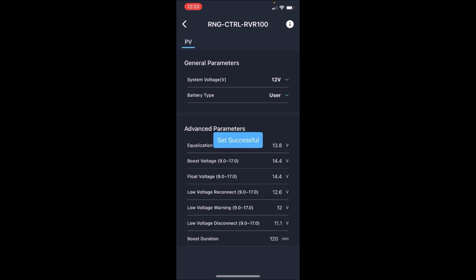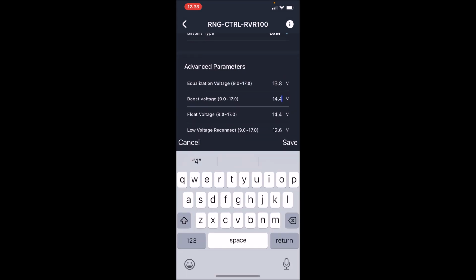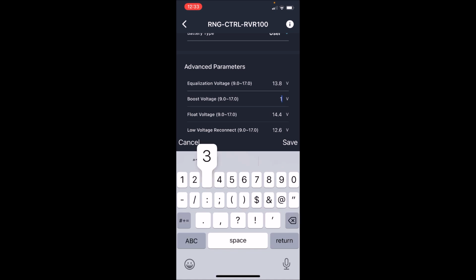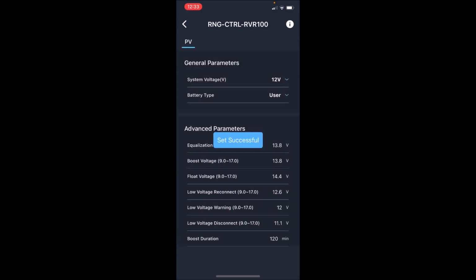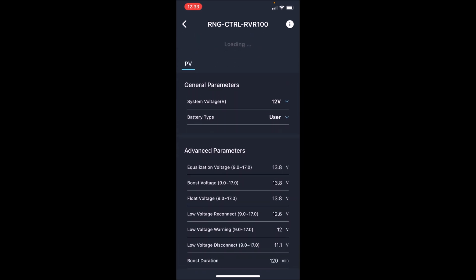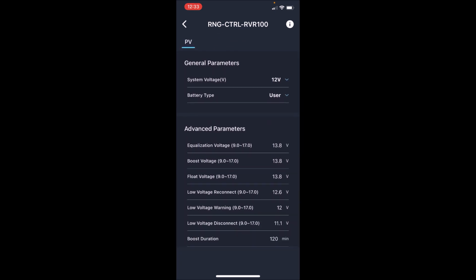And I can change it to 13.8. Now I'm going to save it. Now I'm going to go to the next one, change it to 13.8 and save it. And look at that, it already changed the float voltage for me. So now we're set for 13.8, so the battery bank is not going to charge up above 13.8, so those batteries don't cut off, and they're held at that higher voltage. And when these batteries are held at that higher voltage is when the balancing takes place.